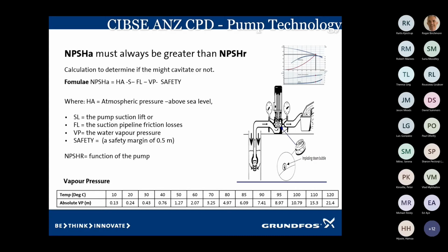The other side of the coin is if you were going to a steam boiler house. If you ever go to a steam boiler house and you'll see a pump pumping water into the steam boiler, the condensate tank which feeds the boiler feed pump is always mounted up in the air. So now we have got a flooded suction. So we take our net positive suction head, which is atmospheric pressure at 10 meters. On top of that, we add the height of the tank, which might be 2 meters. So now we're starting with 12 meters.